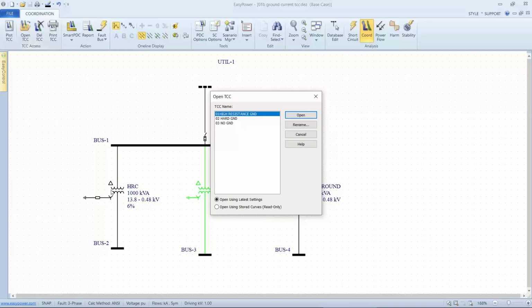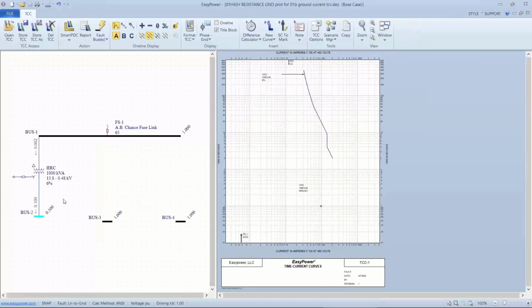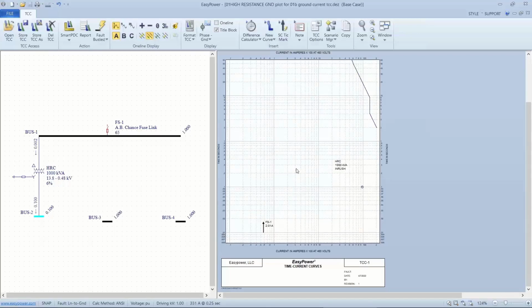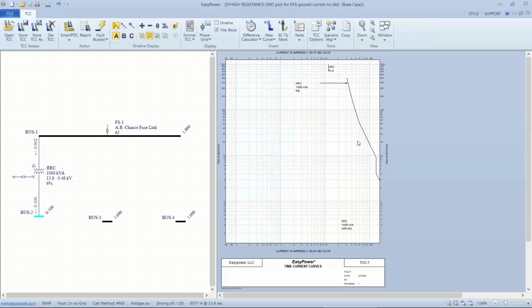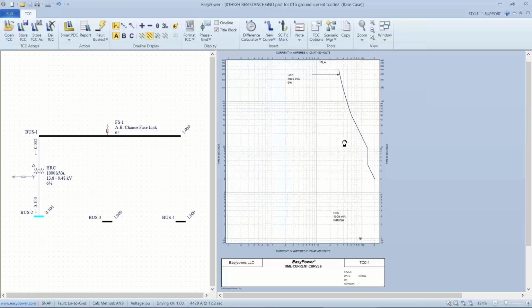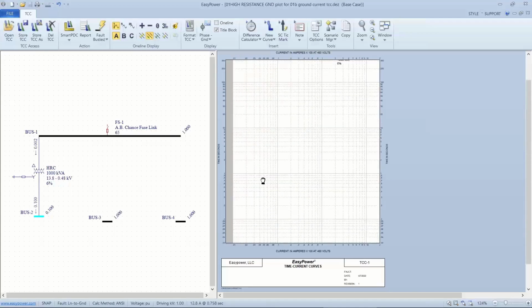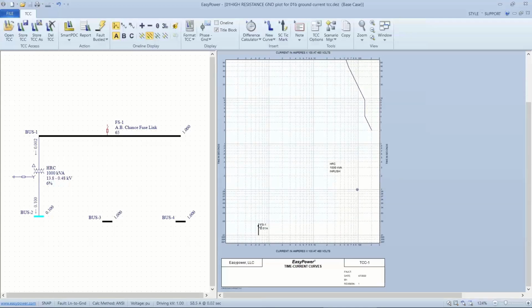Having this resistor in the neutral leg or the ground leg of the Y side guarantees that the maximum current on a fault here will not exceed 100 amps, since it's a 100 amp resistor, which will mean we have a 2 amp fault on the primary. You'll notice we don't show a derating curve. Well, that's because this 2 amp fault isn't anywhere near threatening to damage the core itself. But if I have protection monitoring this, I do need to set my protective relay or fusing to trip at something less than 2 amps.